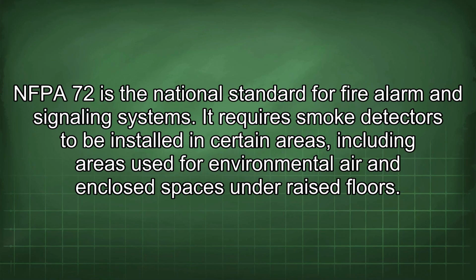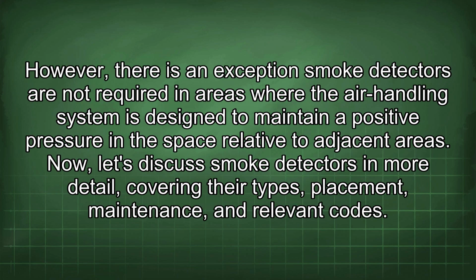NFPA 72 is the national standard for fire alarm and signaling systems. It requires smoke detectors to be installed in certain areas, including areas used for environmental air and enclosed spaces under raised floors. However, there is an exception: smoke detectors are not required in areas where the air handling system is designed to maintain a positive pressure in the space relative to adjacent areas.